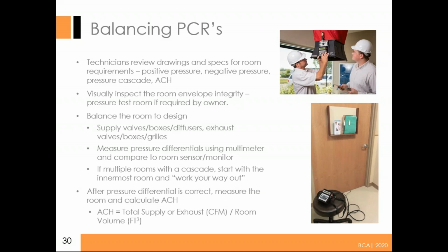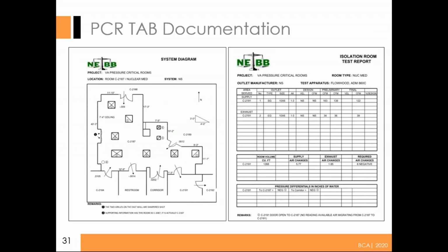I find a lot of, once again, we're generally working with positive rooms, get your supply set up first. That is your pretty much defined number, and then adjust your exhaust as need be after you get your baseline. We can jump to the next page. This is just a representation of a typical balance report, what we use. It's really nothing fancy. The nice thing about computers today is like on our air changes per hour and so forth, we can put the little formulas into the spreadsheets, and you're just typing in your numbers, and it will kick out everything for you as far as your air changes per hour and so forth like that. What we like to do is do a nice little picture with our directional airflows, our room pressures, and then also our differential pressures at the bottom of the report, like this.